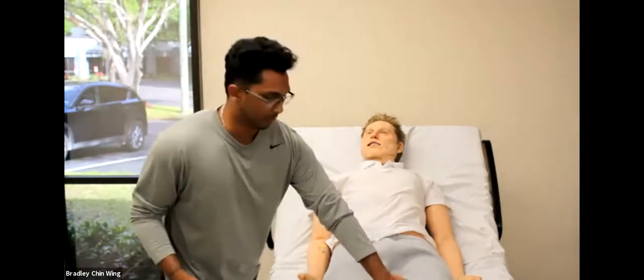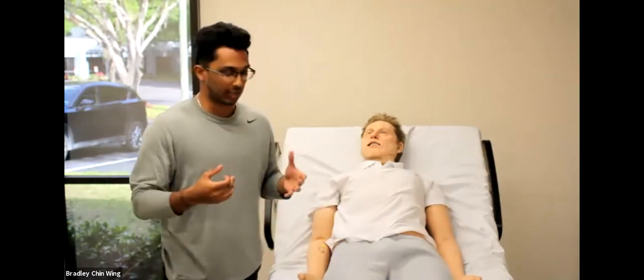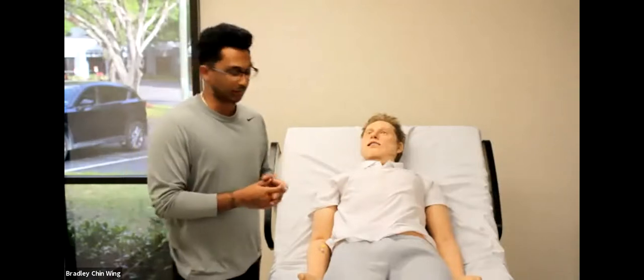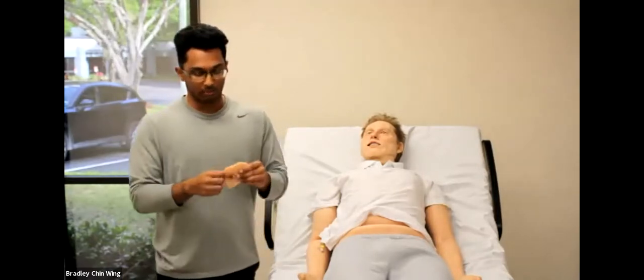He does have genitalia — you can urinate the genitalia and you can catheterize it. If you push a Foley catheter far enough, it will automatically urinate and you'll get actual fluid feedback from the mannequin into the Foley. He also has an IO bone which comes with replacements — it gives you proper resistance of bone and allows you to push fluid through. We also have inserts on both sides representing ribs, so if you want to do procedures such as a chest tube, you have proper resistance and a real bone to manipulate.